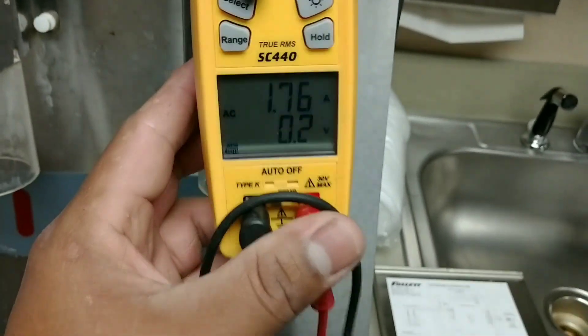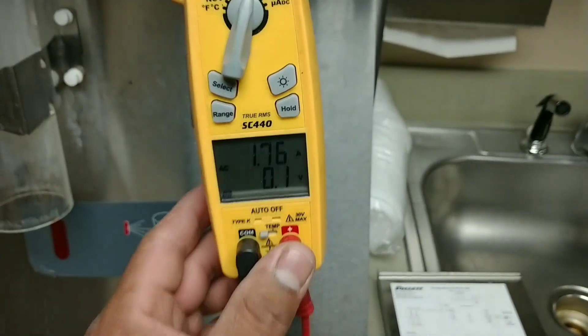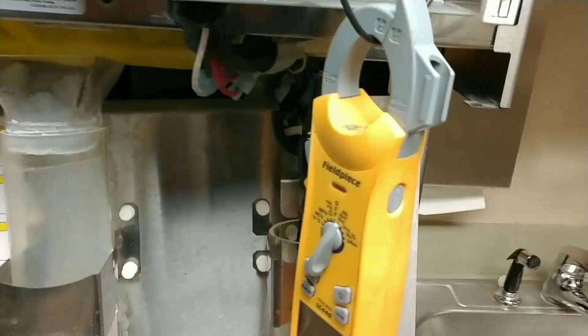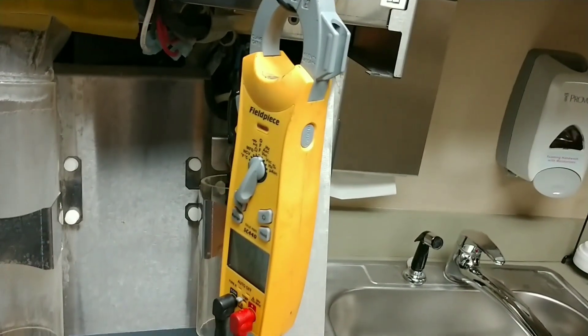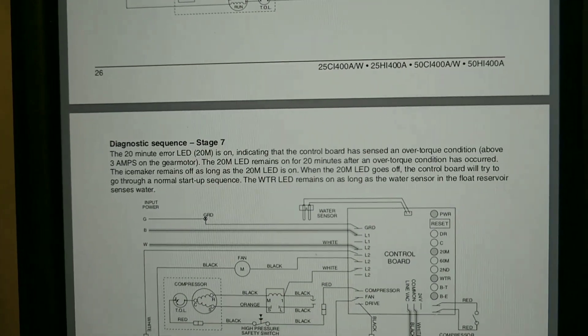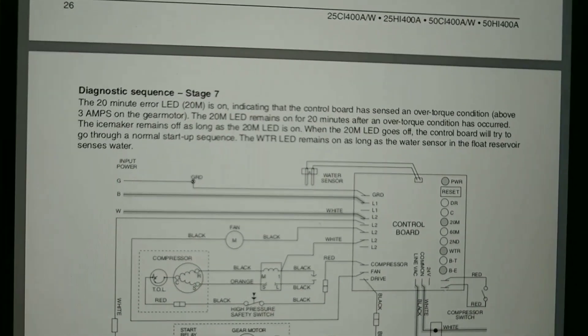I don't remember exactly what the torque rating is supposed to be. I did the bearings on a different machine at this same building. But if you see here, right here it says over torque condition above 3 amps on a gear motor. So anything over, yeah right there, 3 amps right there on the gear motor.